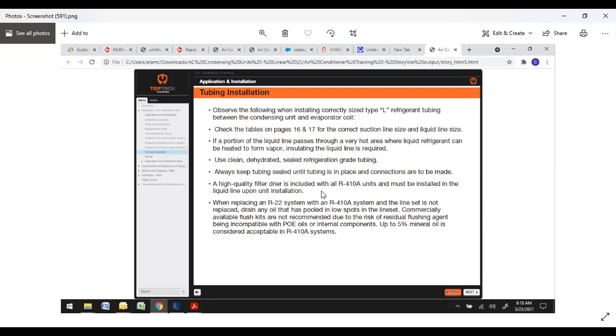Always install a high quality filter drier that will be included with your 410A unit. Must be installed in the liquid line unit. When replacing an R22 with a 410A and the line set is not replaced, clean any oil that is pooled in low spots in the line set. Sometimes you'll end up with some funny line sets that you'll create oil traps. So you got to get all that old oil out of there.